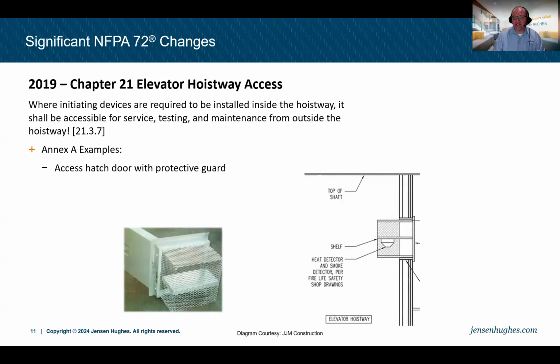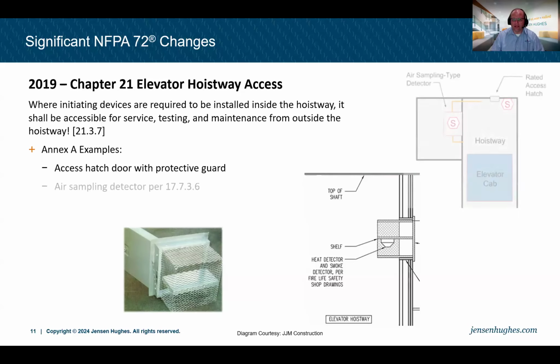Well, one example is just using an access door, like you see with this device. It contains basically a cage that sits within the hoistway. You have a rated access door. The equipment, like a smoke detector or heat detector, might be inside this cage. You can access it from outside the hoistway while maintaining the rating of the wall of the hoistway, and it becomes a nice way to test that device, make sure it works without actually entering the hoistway.